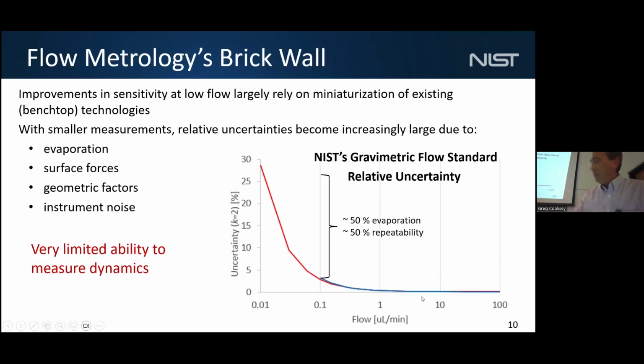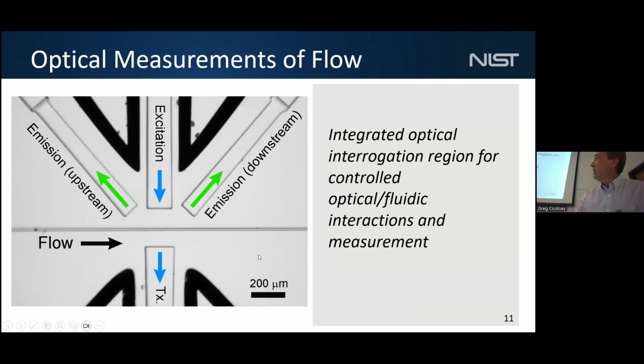So we have a flow channel here coming left to right across an optical interrogation region. We have laser light that we deliver through optical fibers through an internal waveguide to deliver light to a specific region of interest on the microfluidic channel. We can measure the transmitted light through that interrogation region, so we can normalize to the incident power of light. And we can also measure obscuration. If anything moves through, it will block light. We think about that absorbance.